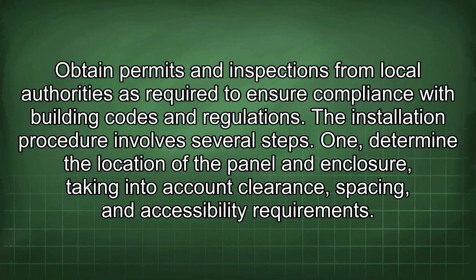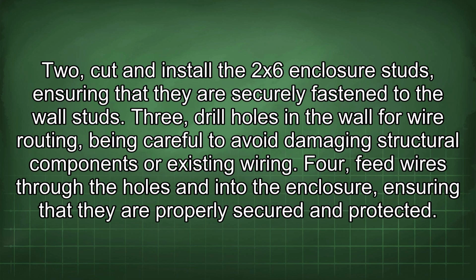The installation procedure involves several steps. 1. Determine the location of the panel and enclosure, taking into account clearance, spacing, and accessibility requirements. 2. Cut and install the 2x6 enclosure studs, ensuring that they are securely fastened to the wall studs. 3. Drill holes in the wall for wire routing, being careful to avoid damaging structural components or existing wiring. 4. Feed wires through the holes and into the enclosure, ensuring that they are properly secured and protected.